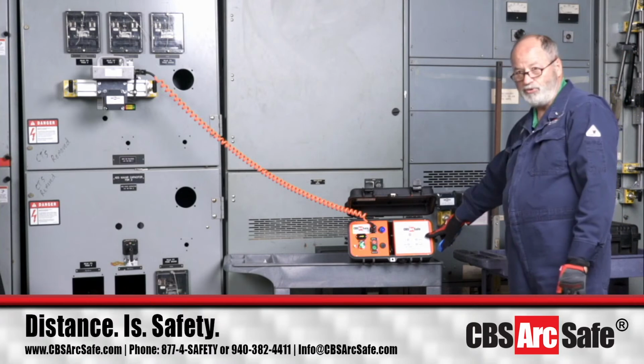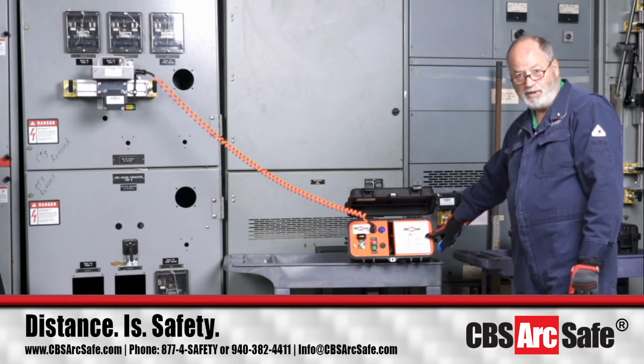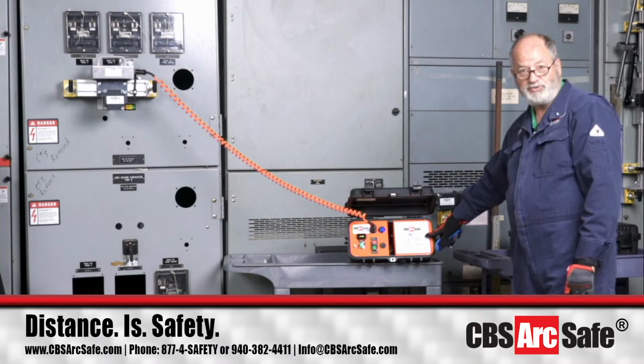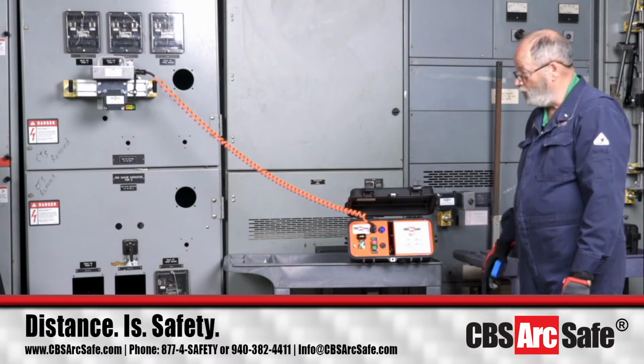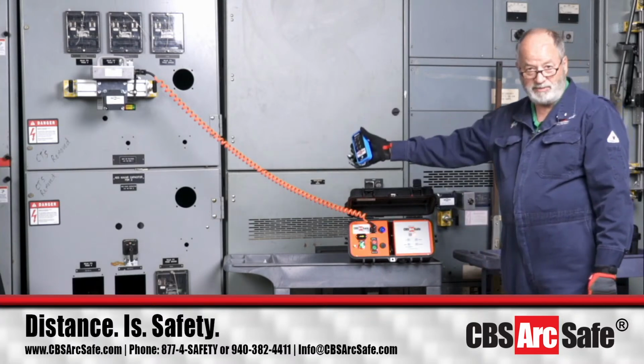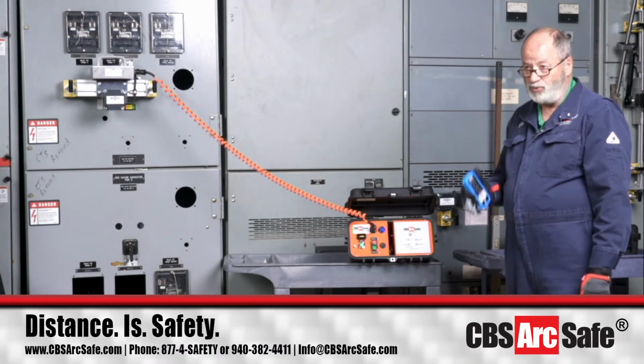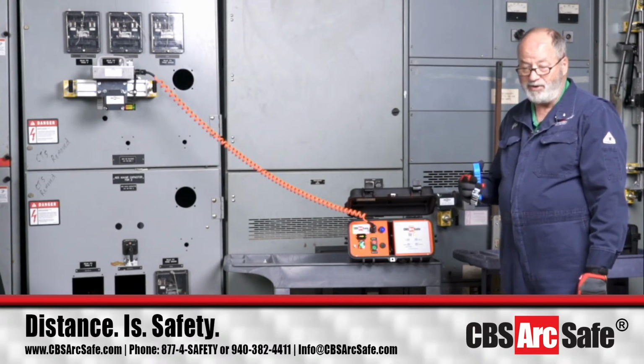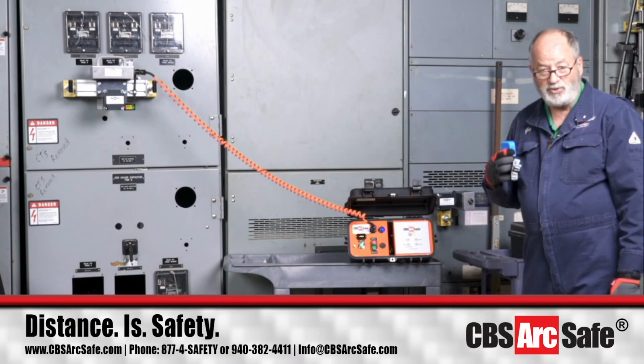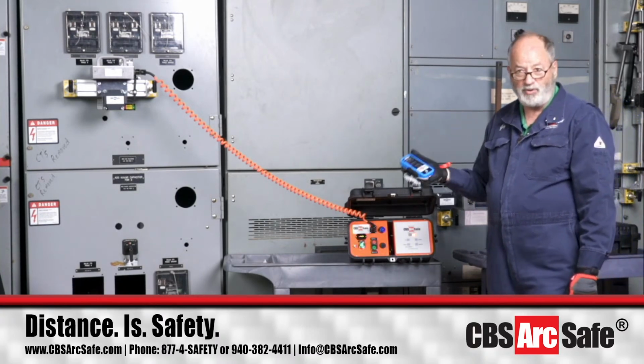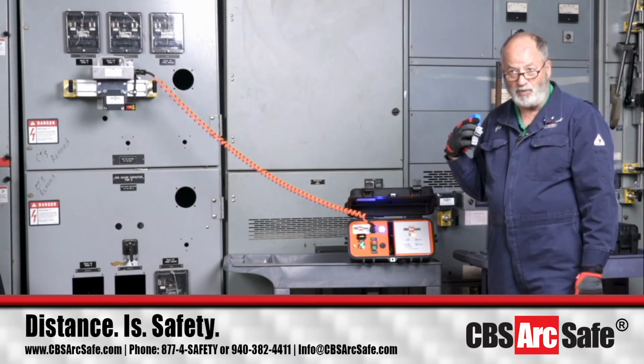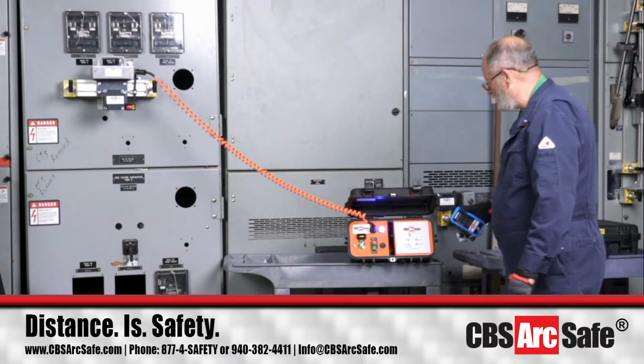We use different torque numbers for an RS3 based on the gearbox on the motor than we would for an RS1. We've determined those torques by using a torque wrench on the system to figure out, for say a 1200, 2000, or 3000 amp breaker, how much torque is required. That way we know not to apply more torque than just a couple of foot-pounds over what's needed to get the breaker on and off the bus.